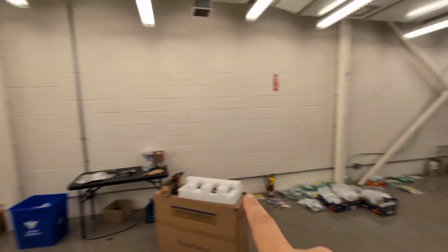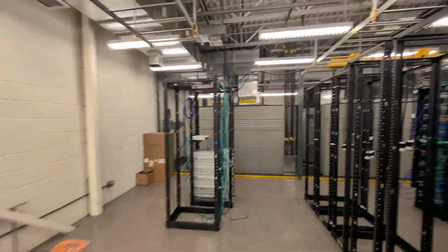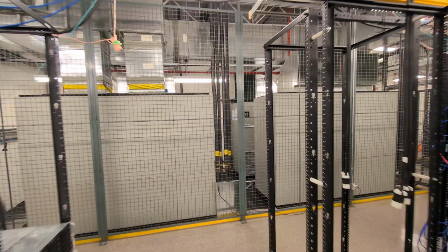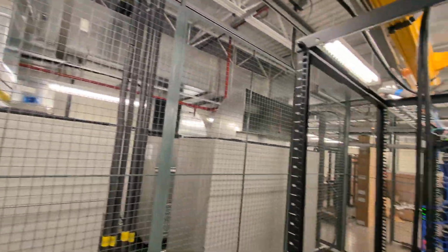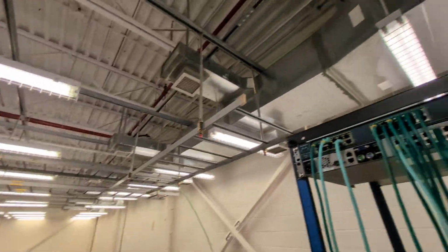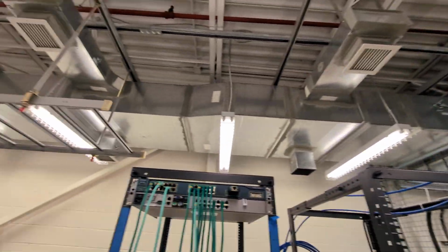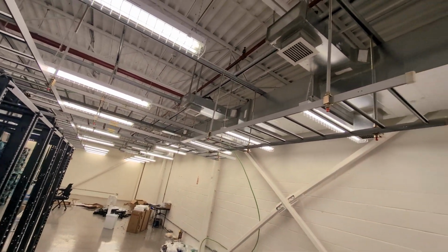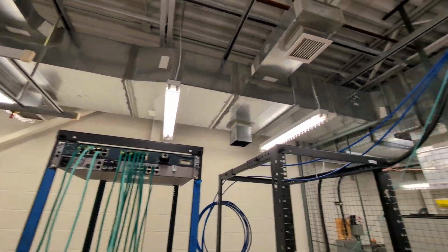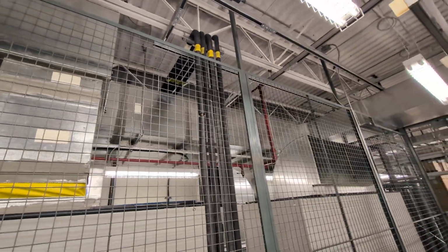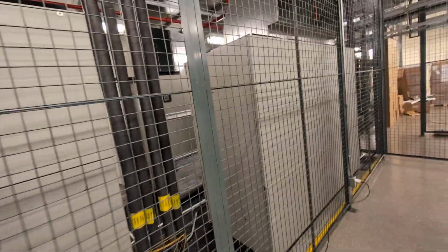So I'm imagining the cooling unit will probably go here, probably one here, another one at the back. This is currently where the CRAC units are. There's 4 CRAC units back here. 2 of the units go directly into the space. The other 2 go into the ductwork. As you'll see, the ductwork kind of comes up here, spread around. The entire top floor is fed by this ductwork, as well as there's one small run that goes downstairs. There's no independent cooling control downstairs, so you just kind of have to balance it manually, which doesn't work very well.